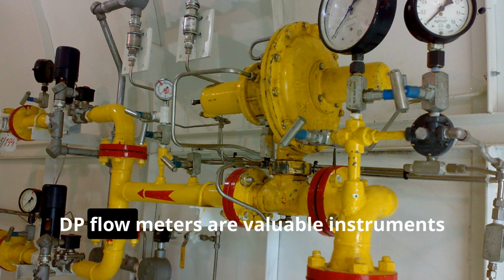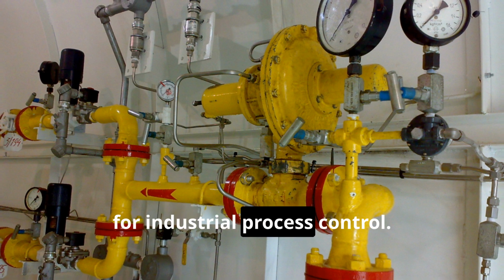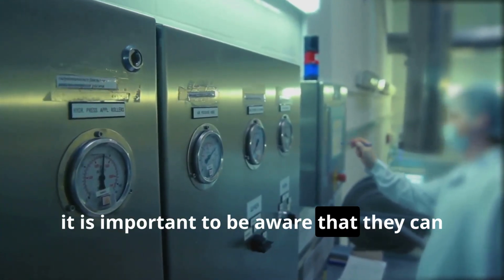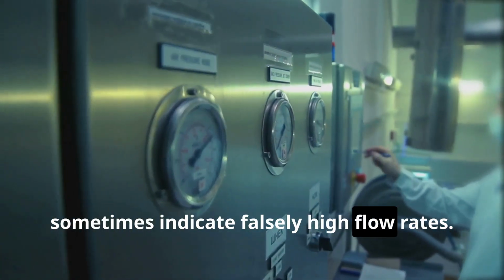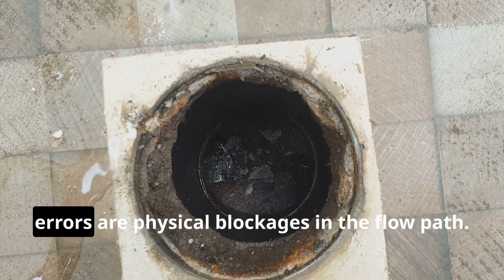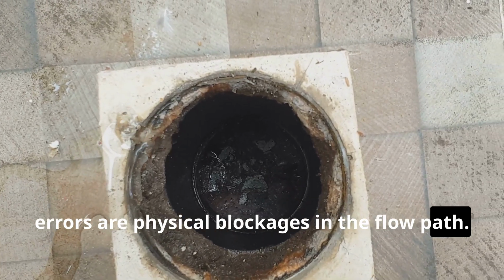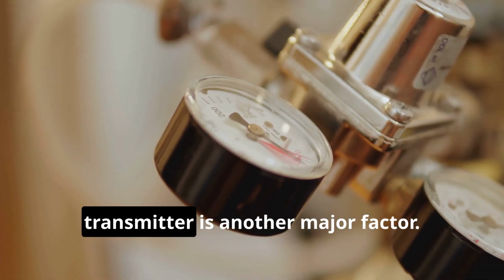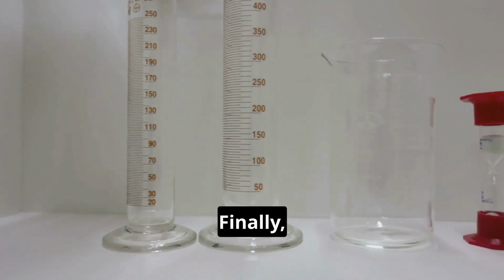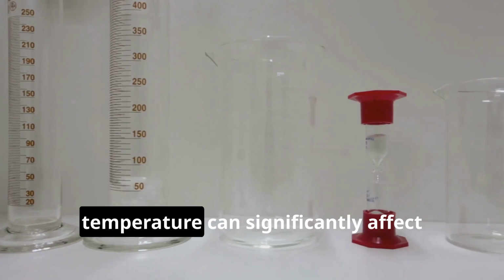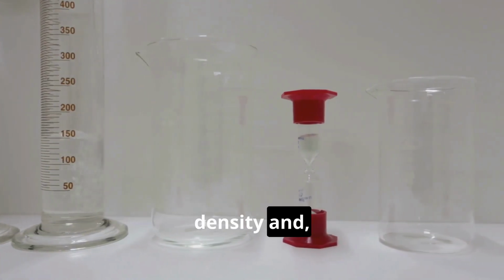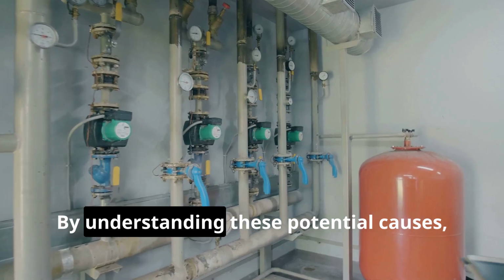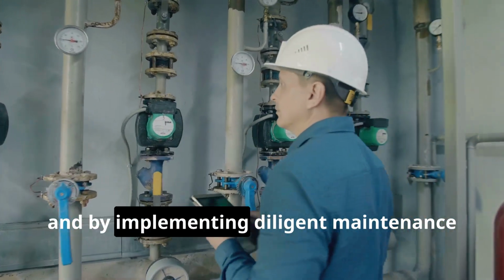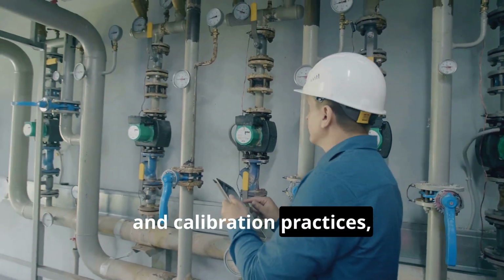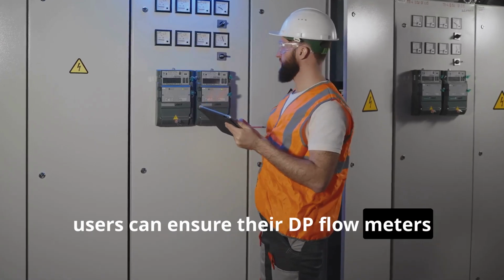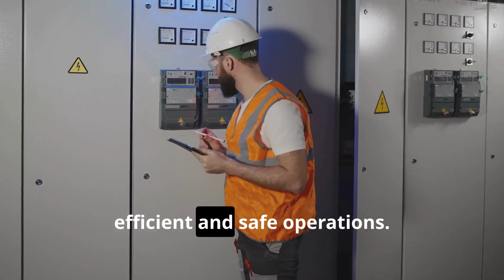In summary, DP flow meters are valuable instruments for industrial process control. However, it is important to be aware that they can sometimes indicate falsely high flow rates. The most common culprits behind these errors are physical blockages in the flow path. Incorrect calibration of the DP transmitter is another major factor. Finally, uncompensated variations in fluid temperature can significantly affect density and, consequently, the flow reading. By understanding these potential causes, and by implementing diligent maintenance and calibration practices, users can ensure their DP flow meters provide reliable and accurate data for efficient and safe operations.